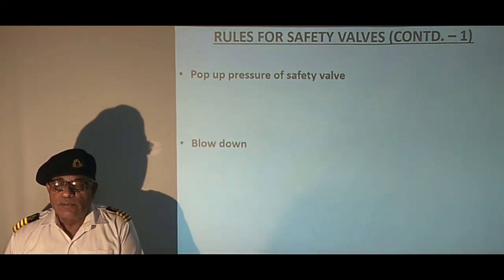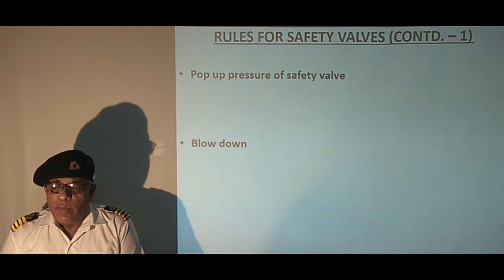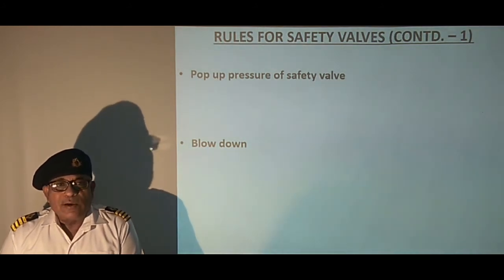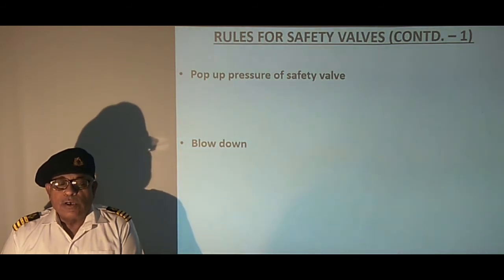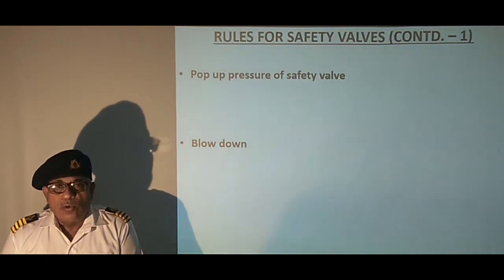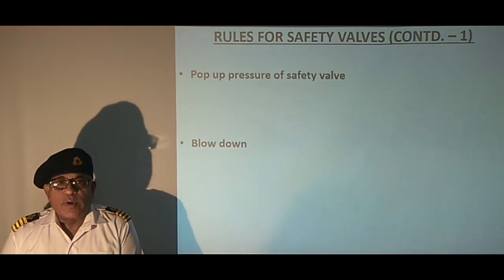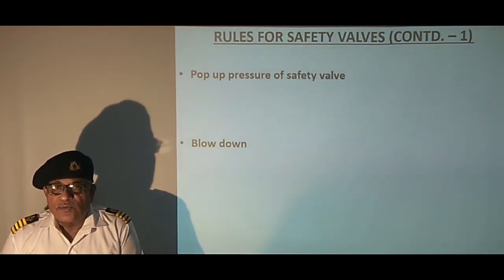The next is blow down. Pressure drop between opening and closing pressure is called blow down. Maximum blow down as per regulation is 5%, although it is usual to set the blow down at 3% to prevent excessive loss of steam.